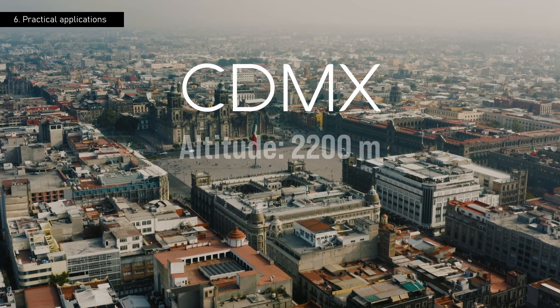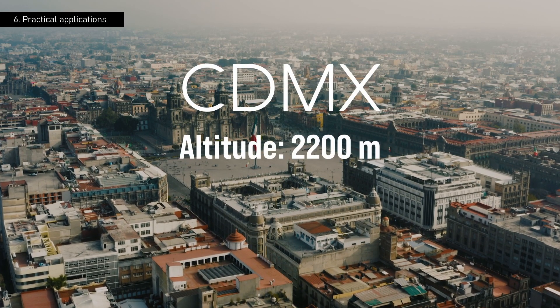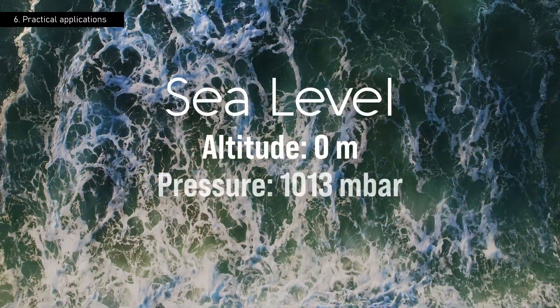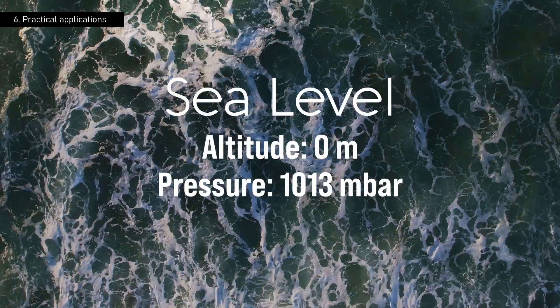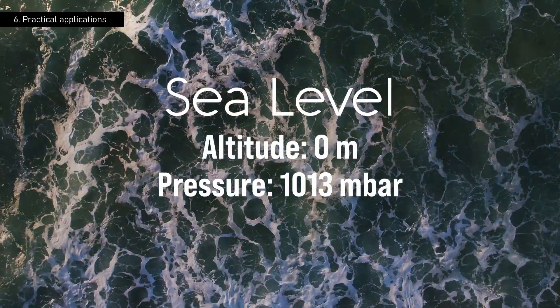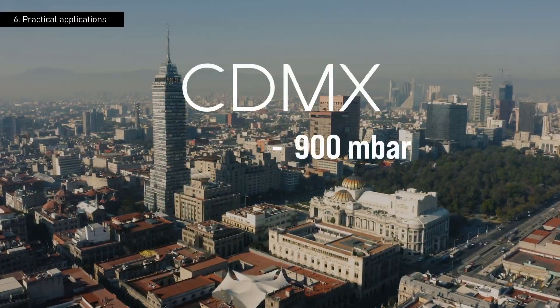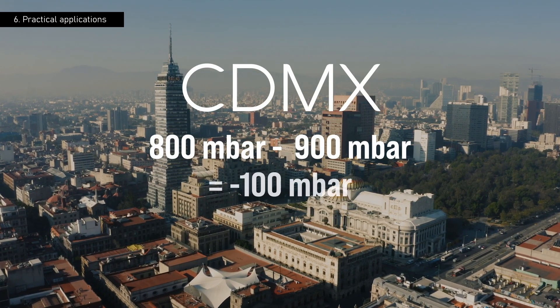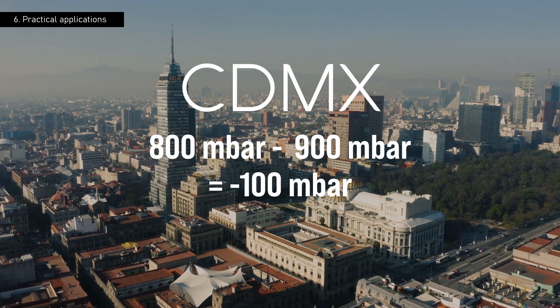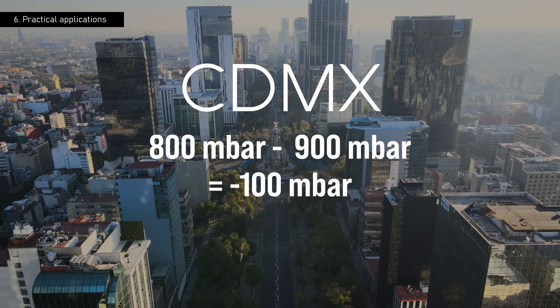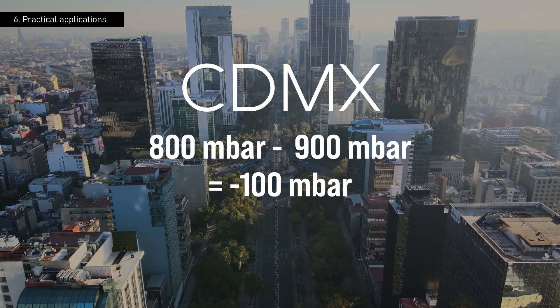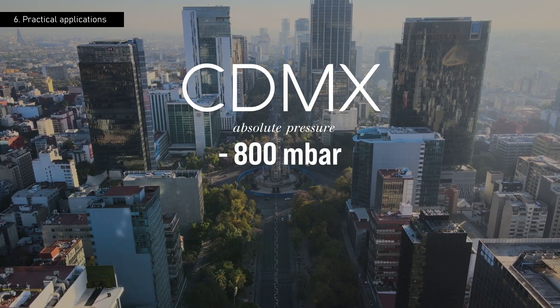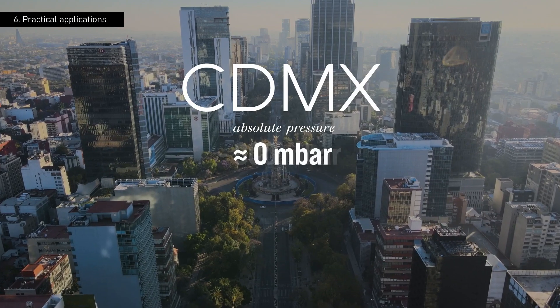First, we must understand that the atmospheric pressure in Mexico City is 800 millibars, compared to the typical 1,013 millibars at sea level. Attempting to generate a relative vacuum of minus 900 millibars in Mexico City, with an atmospheric pressure of 800 millibars, would involve trying to reach a pressure lower than absolute zero inside the chamber, which is physically impossible. We could reduce the 800 millibars of atmospheric pressure to nearly zero, but never beyond this.